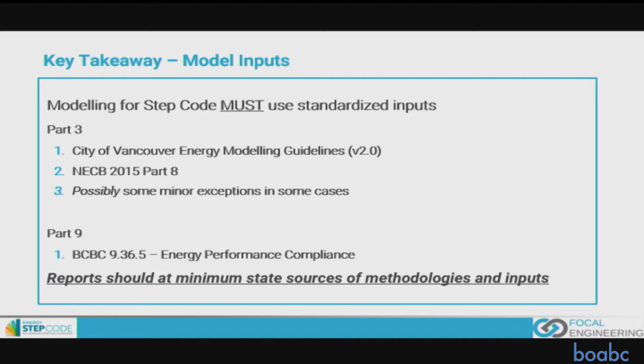I think some people might be uncomfortable with me throwing this in here, but I think that if you have a one-size-fits-all solution, inevitably you're going to run into situations where it doesn't fit. One example I have is affordable housing building. So we're modeling against a standard multi-use residential building, but then our building has a commercial kitchen in it because there will be meals provided for the people living there. That's a huge heating load, especially for the size of the building because it's fairly small with the kitchen ventilation. The archetype building didn't have that in it, so it's not necessarily fair for us to compare directly against that.